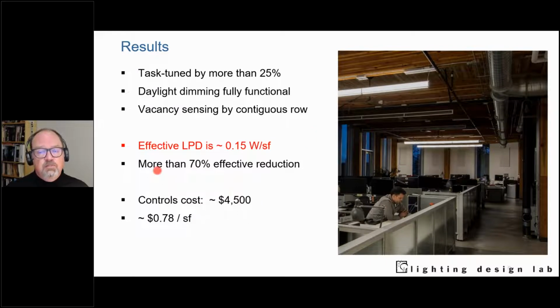We had more than 70% energy savings. Right now the effective lighting power density is about 0.15 watts per square foot. This is an outlier though, because it's such a beautifully daylighted building populated with people who actually pay attention to lighting controls and energy use. More common energy savings for these systems tend to be in the 45 to 55% range, but this shows what's possible.